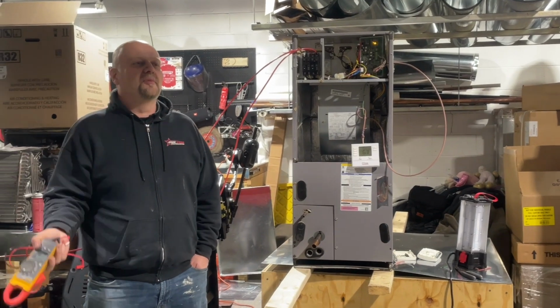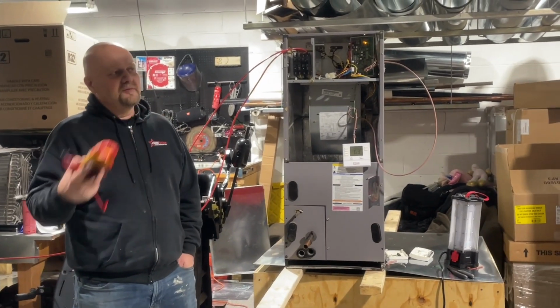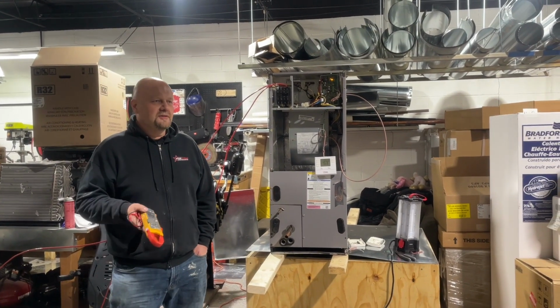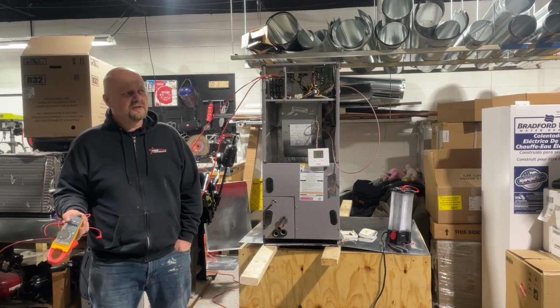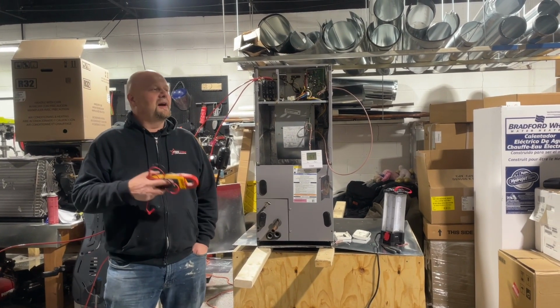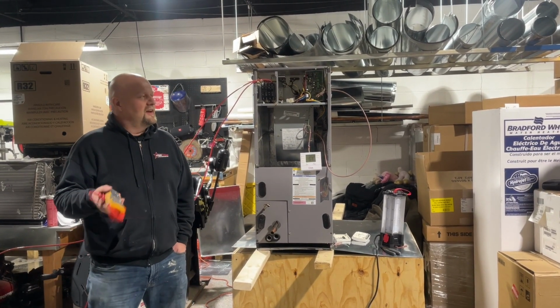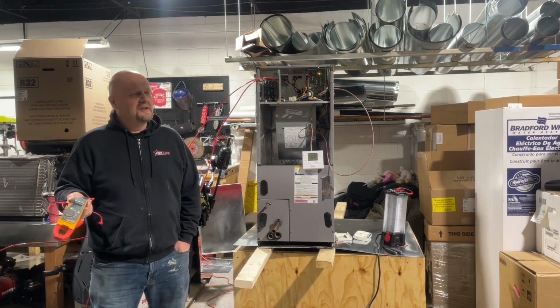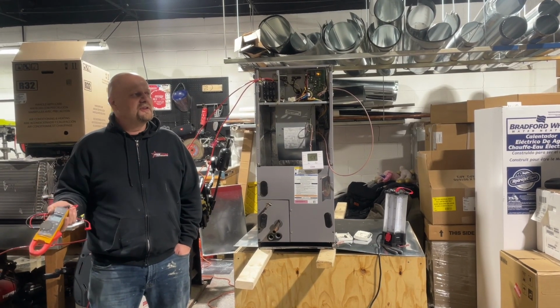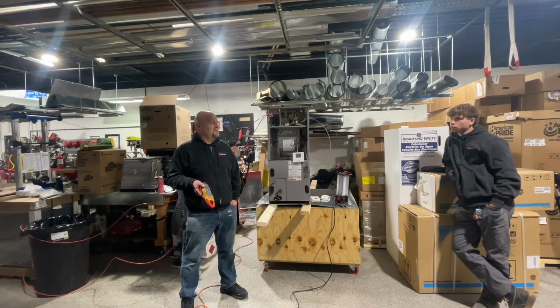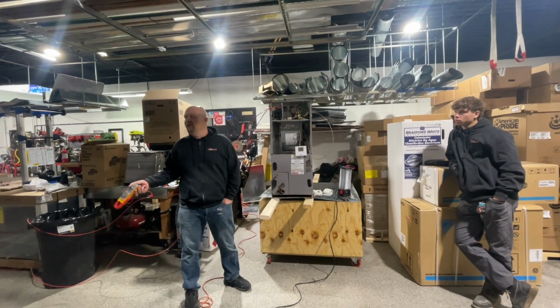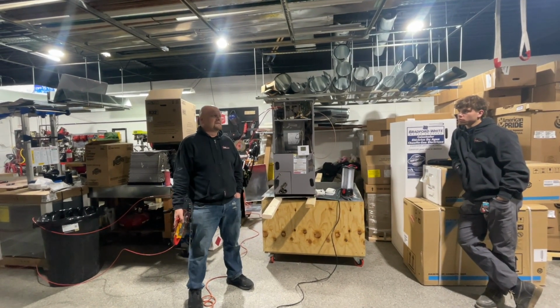The good numbers to remember are this: voltage times amperage equals wattage. So that's how you get the kilowatts. That's the power achieved. And then to know how many BTUs, kWs times 3,412 is your actual BTUs. So BTUs are important because that's how we know how much heat we get for something.